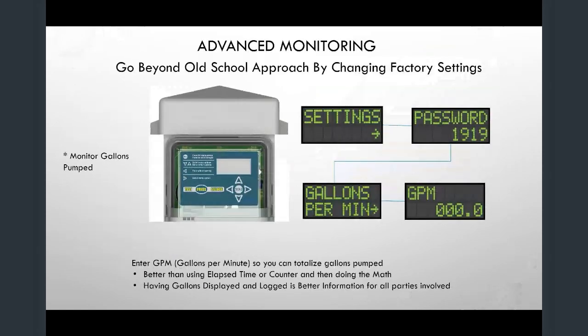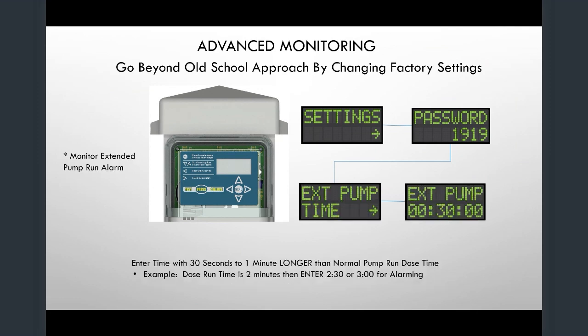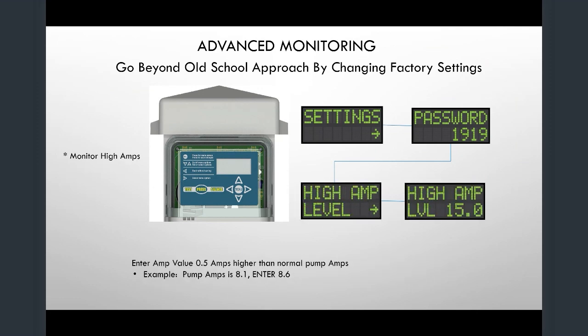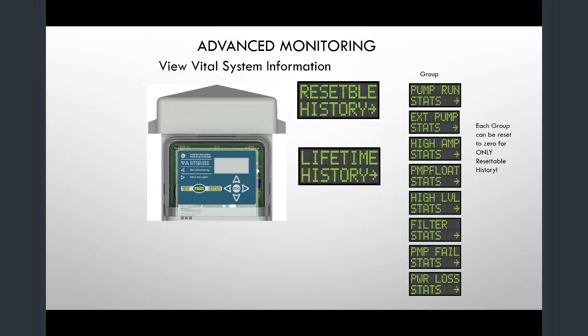Just kind of goes through diagrams and how it works and how to calculate drawdown. You can do a drawdown test to see how many gallons per minute your system actually draws. Extended pump run, high, you can set your high amp levels. It's the menu structure. We have a resettable history and a lifetime history. So the lifetime history, all of the stats stay in there for the lifetime of the panel.